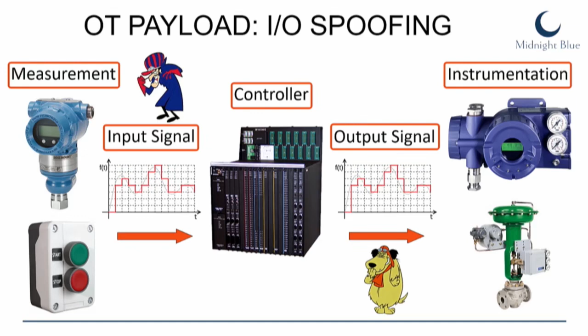So it could have been, for example, an I/O spoofing scenario — a scenario where we want to do spoofing of input and output values. As you can see here, you have measurement values that come as an input signal to the controller, and as an output signal go to the instrumentation. Then we want to mess with either the input or the output to cause some unsafe state.